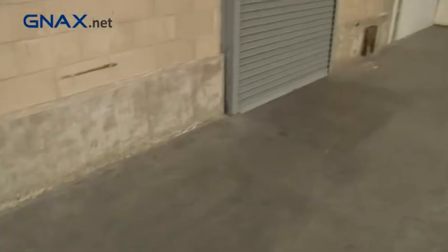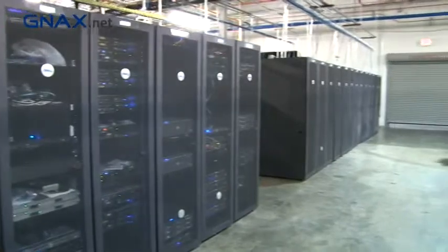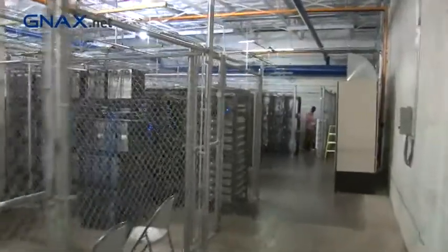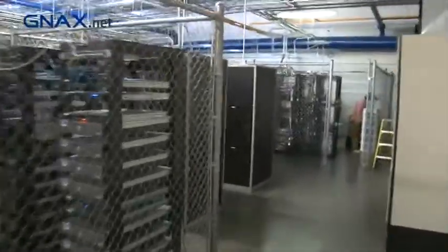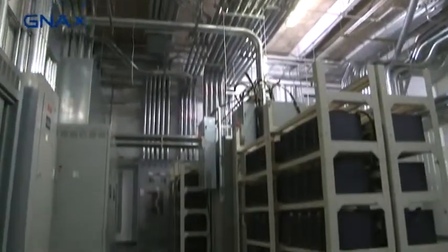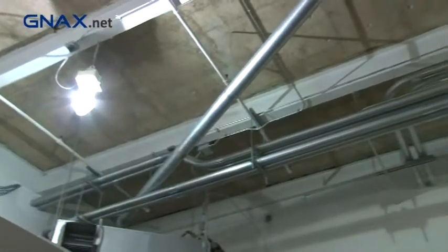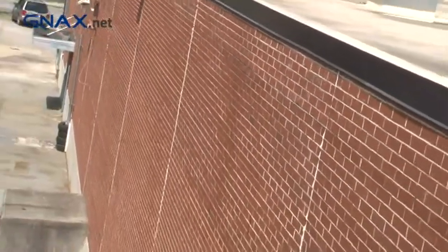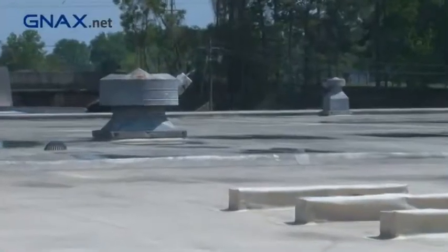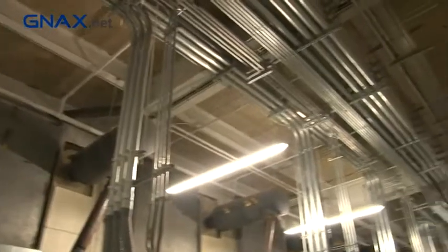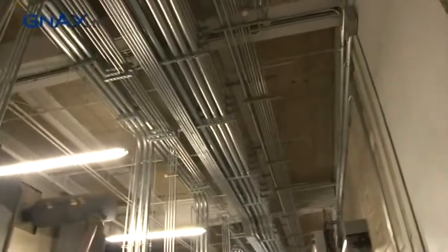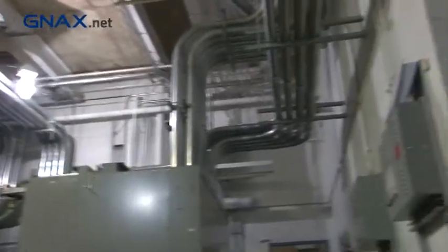The AtlantaNAP building infrastructure has several key advantages for use as a data center. First, the floors are concrete 10 inches thick with 1-inch rebar, giving us the ability to handle complex loads, including batteries and IT equipment, without doing studies on them. The walls are CMU with a solid brick exterior and are not load-bearing. The roof is all concrete, either pre-stressed concrete plank or a solid poured concrete roof, giving good wind load resistance as well as damaging hail resistance.